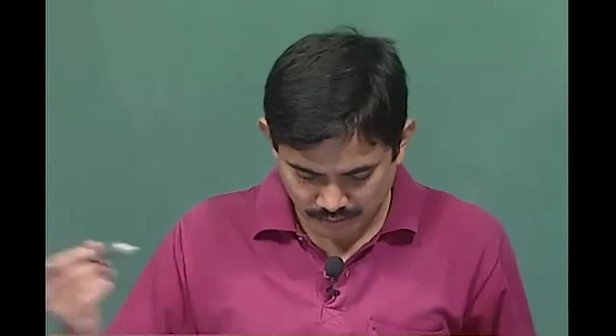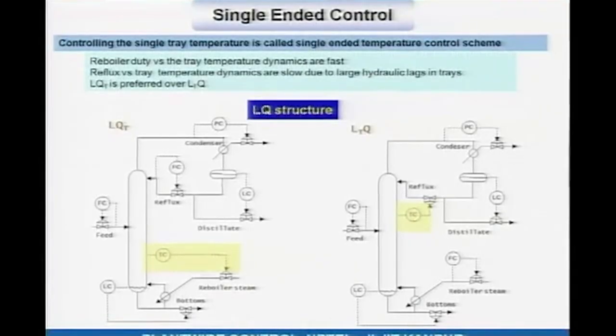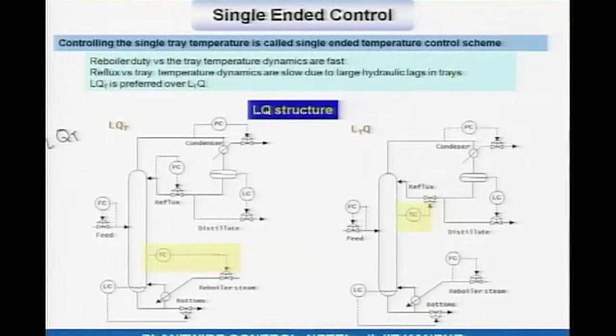Of course, composition measurements from quality assurance labs also have a role to play, but we will not go into that now. Degrees of freedom is 2. I could have one of the tray temperatures adjusting one of those degrees of freedom. For example, with an LQ basic structure, I can use Q to control a tray temperature, fix the reflux at a reasonably high value so that heavy key does not end up in the distillate even for the worst-case disturbance, and then adjust Q to hold a stripping tray temperature constant. This is the LQT structure.